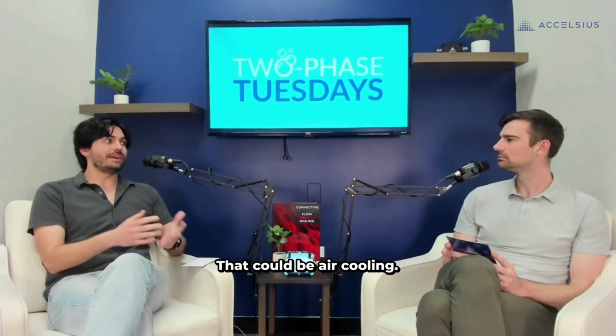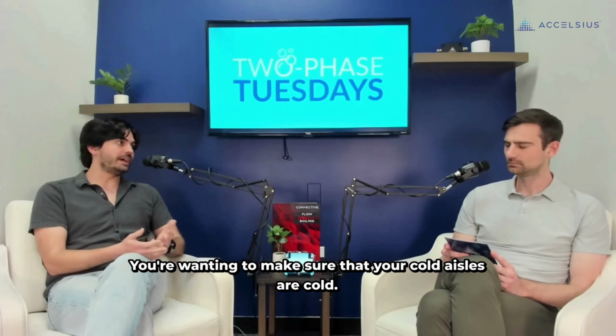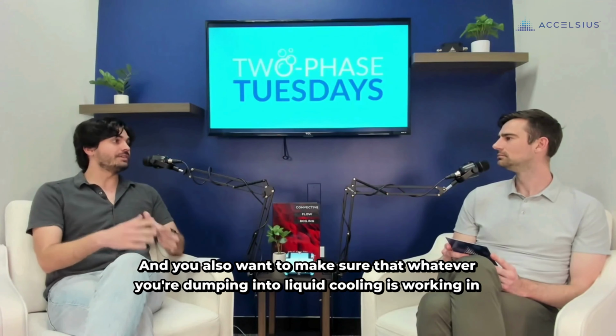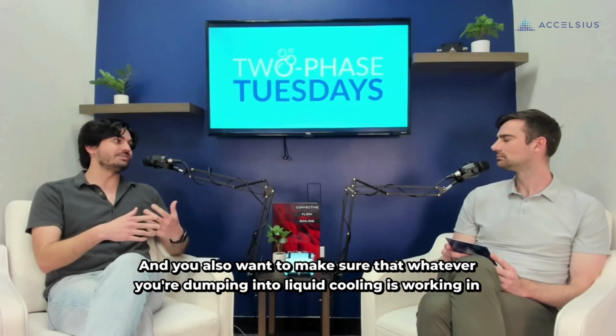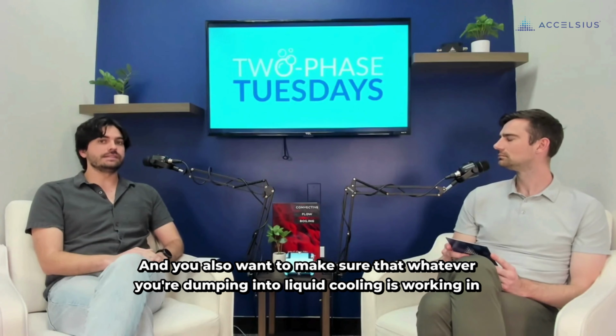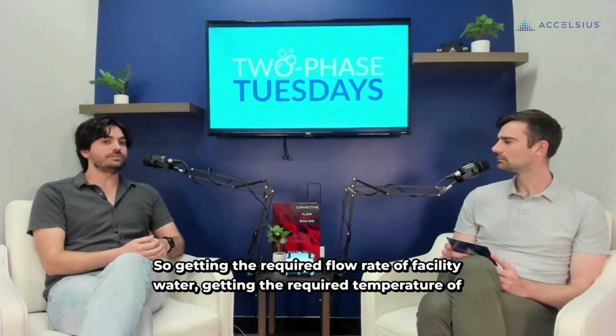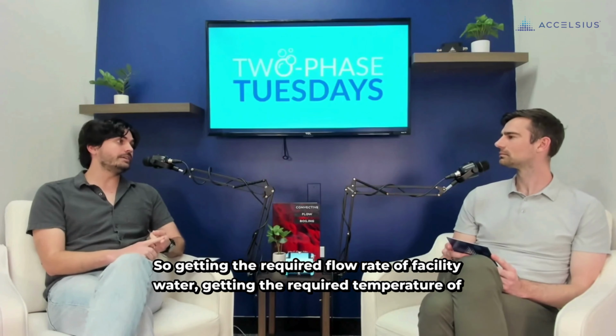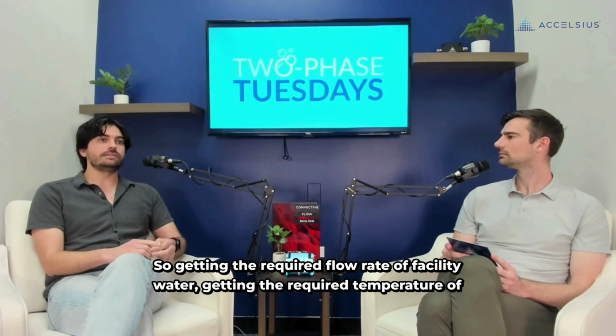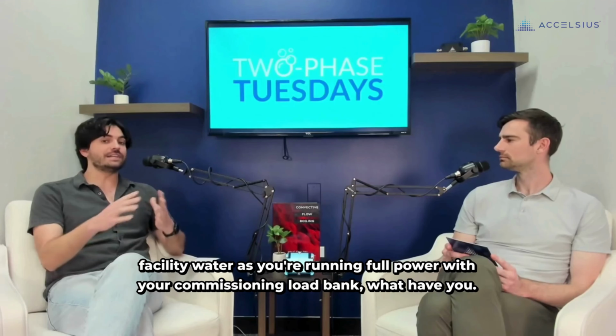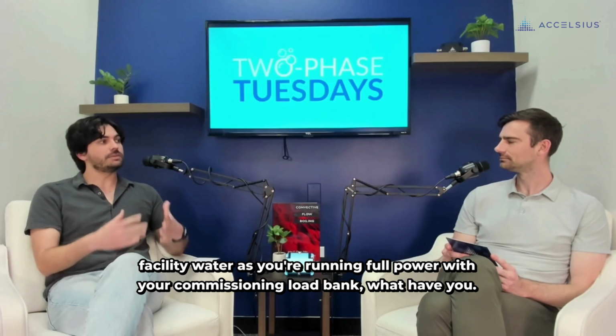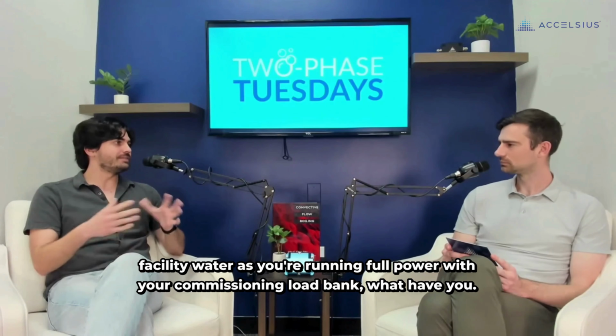That could be air cooling or liquid cooling. You want to make sure your cold aisles are cold, your hot aisles are hot, your air is flowing where you want it, and that whatever you're dumping into liquid cooling is working too, getting the required flow rate and temperature of facility water as you're running full power with your commissioning load bank, or whatever.